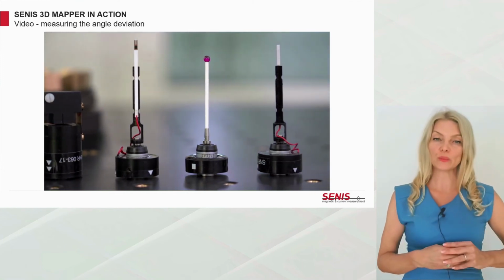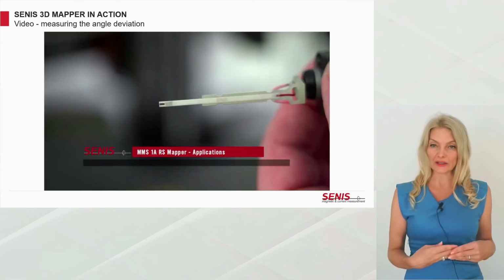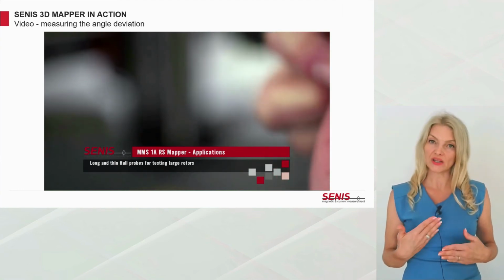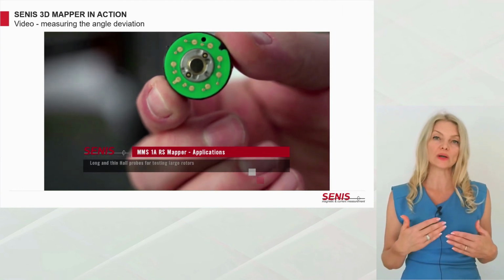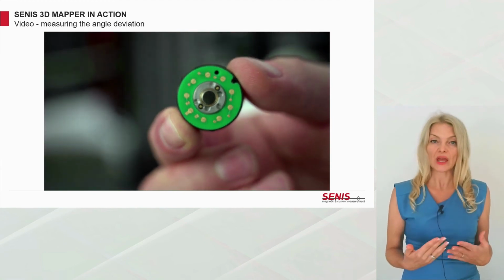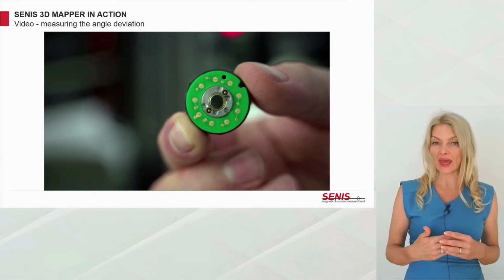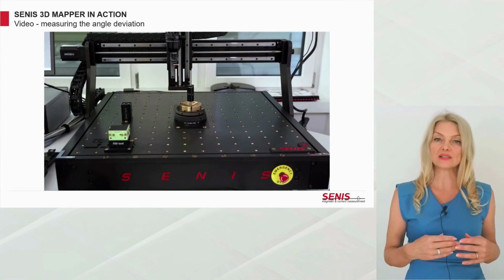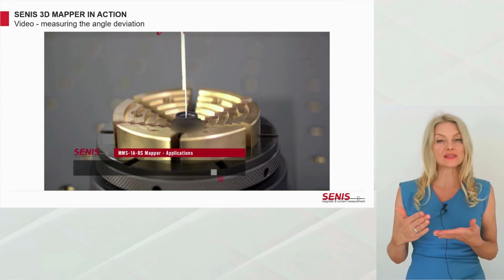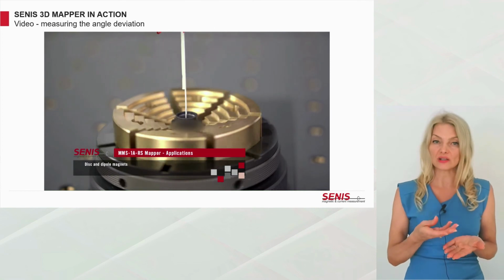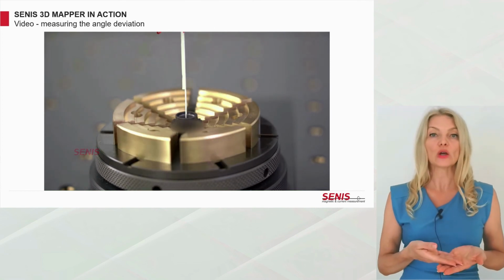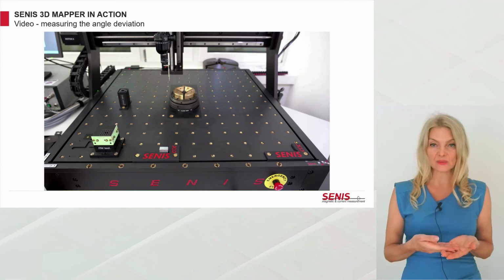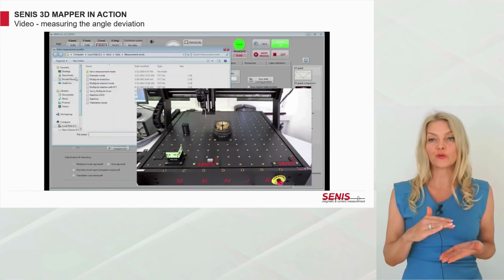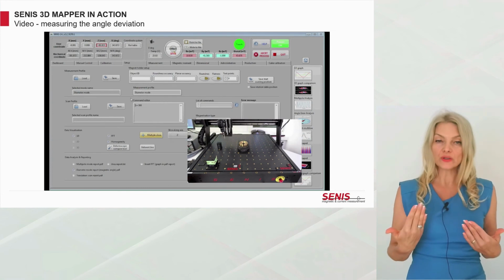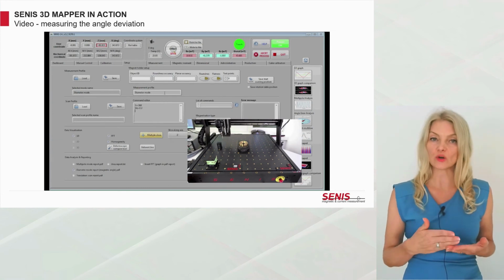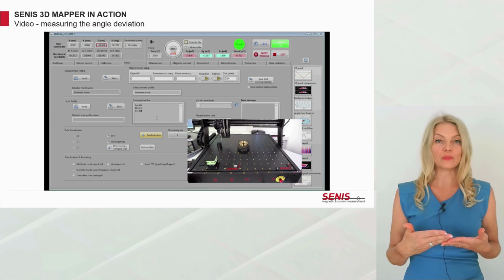The 3D Hall probe is mounted on the mechanical moving platform. The mapper probes are easily interchangeable due to a smart touch sensor. To measure the angle deviation, the magnet is positioned on the rotary stage so that the geometrical center is well aligned with the rotation axis. The magnet is rotated 360 degrees, and during the rotation all three components of the magnetic field are measured.